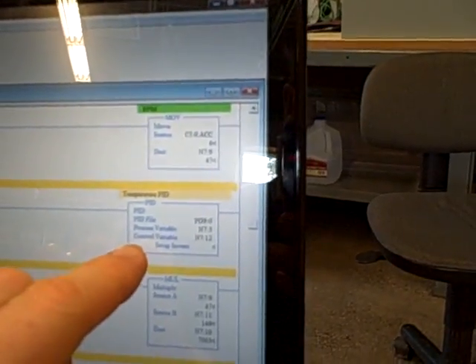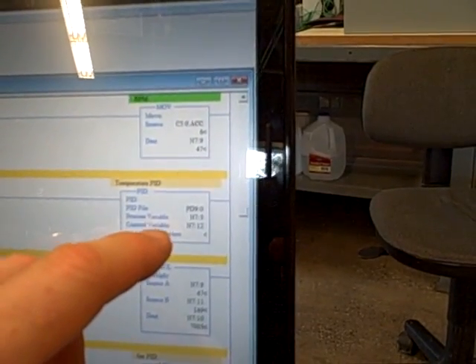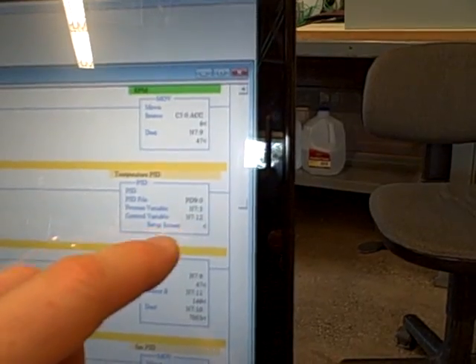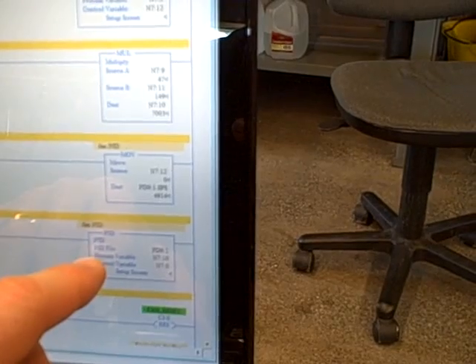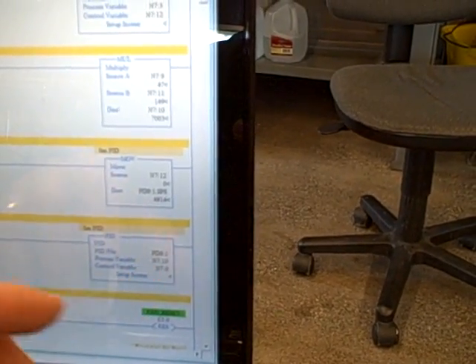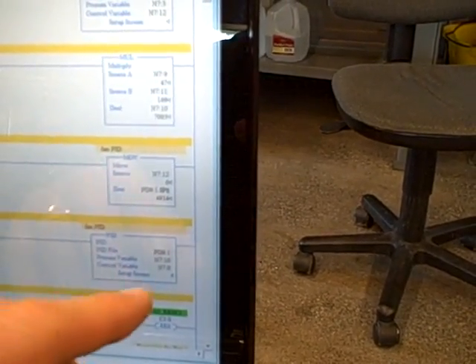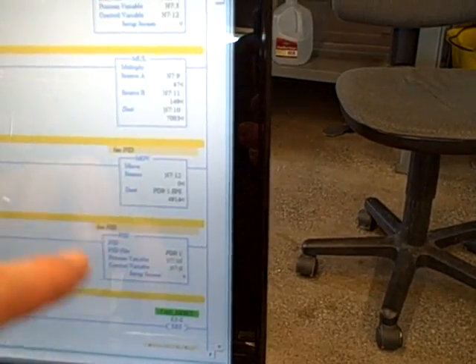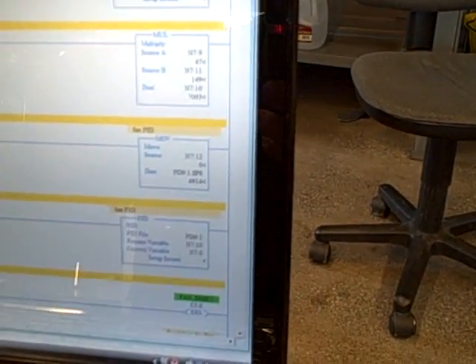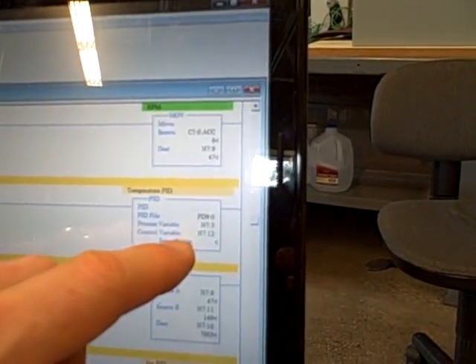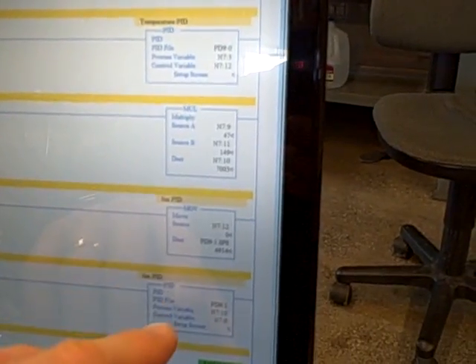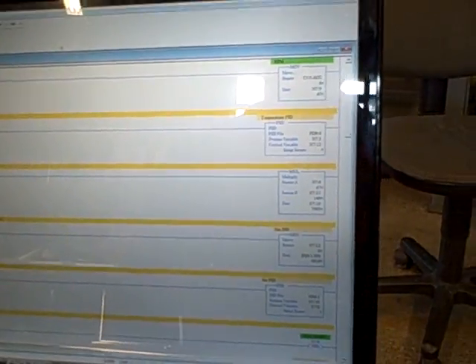Here's how we do it — we simply assign the proper addresses. Right here on the temperature PID instruction, the control variable output goes to register N7:12. When we come down to the fan PID, the process variable is N7:10, and two registers away from that, N7:12 is the set point in the data structure of this PID instruction. Simply by pointing the output variable to the right memory address register, we send the output of the temperature controller to become the set point of the air flow controller. It's as simple as that — cascade control in an Allen-Bradley using PID instructions.